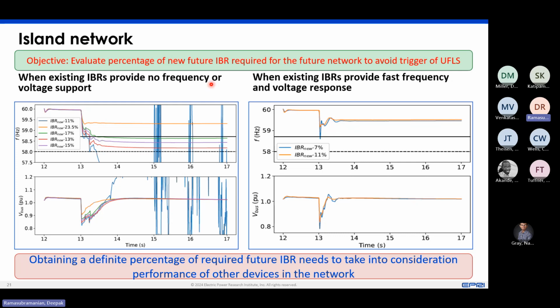We found that if your existing inverters provide no frequency or voltage support, essentially legacy inverters, then to meet the under-frequency load shed criteria you would require around 23.5% of new inverter technology. But if the existing inverters' capability is utilized better, providing fast frequency and voltage response, the percentage of future inverter needed drops to potentially around 7%.